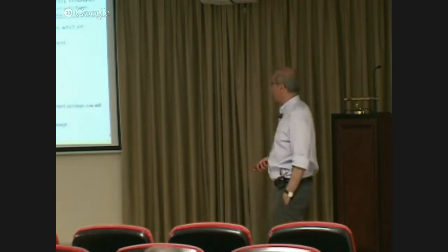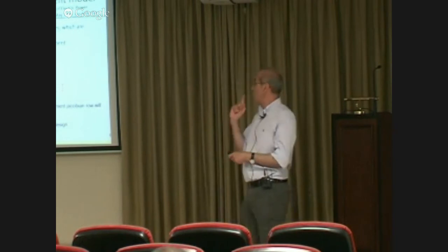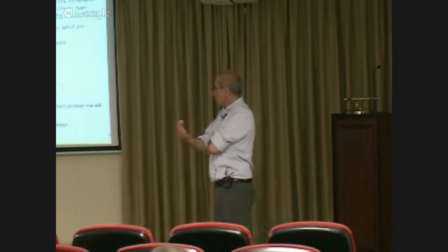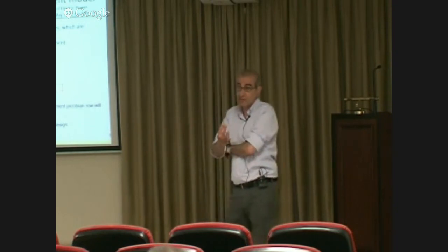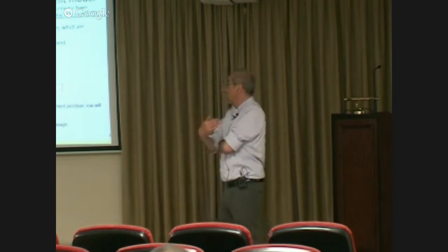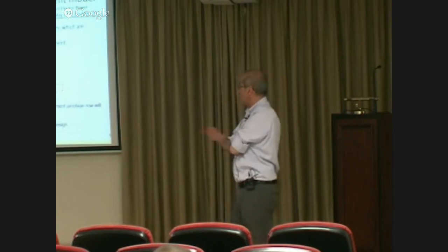Now, before we look into it with the phasor measurements, let me say a few things about leverage points. What do we mean by leverage points? Those of you who may know what critical measurements are: critical measurements are the measurements which are needed for observability. In other words, if you lose a critical measurement, you lose observability. And of course, you don't want to have critical measurements, because if you have bad data on a critical measurement, since it's needed to make the system observable, that bad data cannot be detected. So all critical measurements are vulnerabilities for the system. Critical measurements, we know, are bad, and we can easily identify them. We know that they shouldn't be in the measurement set.